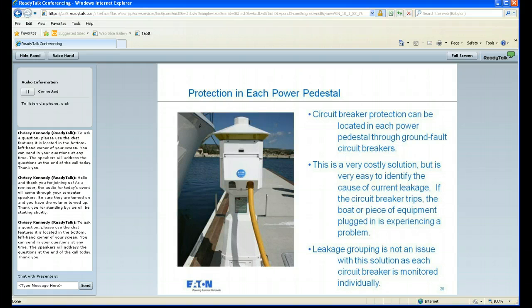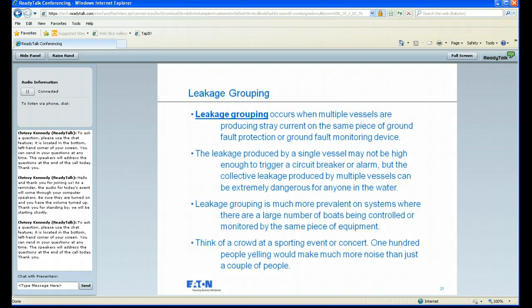You can also provide protection in each power pedestal through GFI circuit breakers on each unit. This is a little bit of a tricky installation or monitoring device because the GFI circuit breakers are much more expensive than a standard circuit breaker, but you will be able to identify the culprit of the leakage into the system very easily with this solution. If a circuit breaker trips on a piece of equipment in good working condition, you know that's the boat or the piece of equipment that's causing the leakage into the water. Again, it's a very costly solution, but much easier to identify who's causing the problems within the marina. Also, leakage grouping is not an issue with this solution, as each circuit breaker is individually monitored. So if you've got an issue with an alarm or a breaker tripping that's GFI protected, you know that boat or that piece of equipment is what's causing the damage.